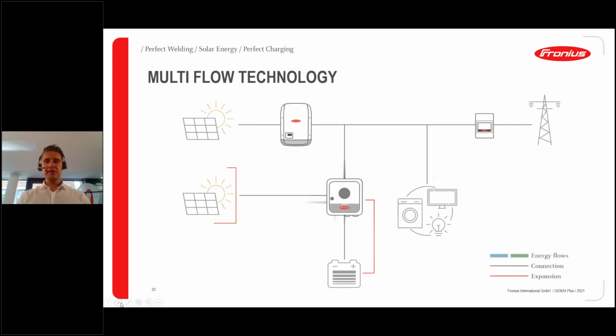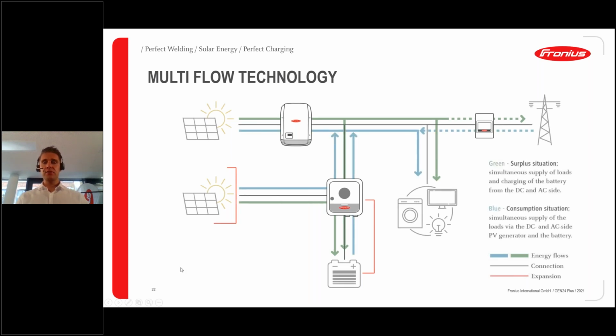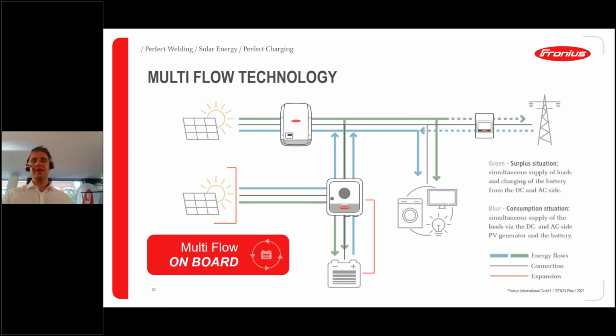You see here one system. I will also demonstrate this to you. That's also, I would say, a common case here in Austria, that customers call you who have got an existing PV system. It must not necessarily be a Fronius inverter, it can be any other third-party inverter as well. And there is also, of course, any time the option to realize AC coupling, which you can see here. You see here on the AC bus of the already existing inverter, we now install the Fronius GEN24 Plus, maybe with a battery, maybe with a PV generator extension here. And then also Multi Flow is available. You see here all the energy flows, all directions, all simultaneous flows are centralized and handled by our Fronius GEN24 Plus inverter.